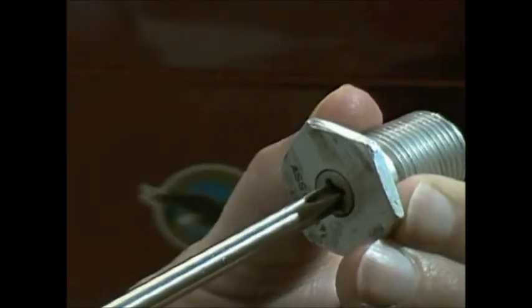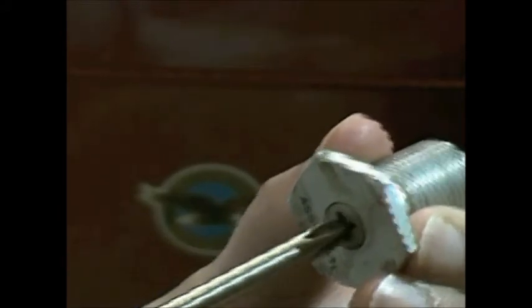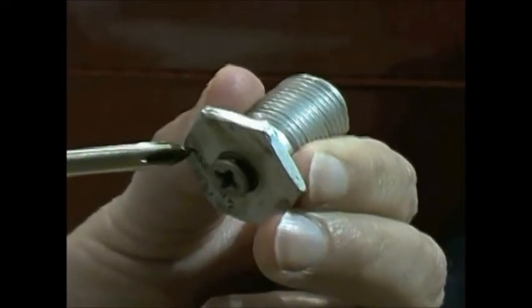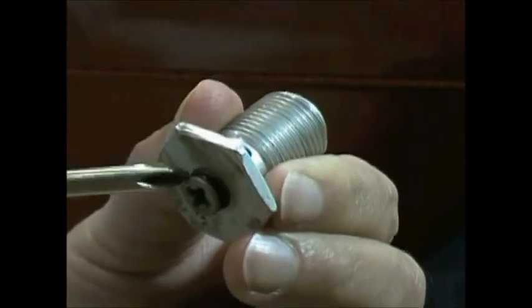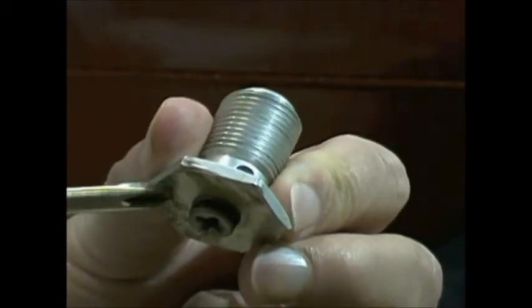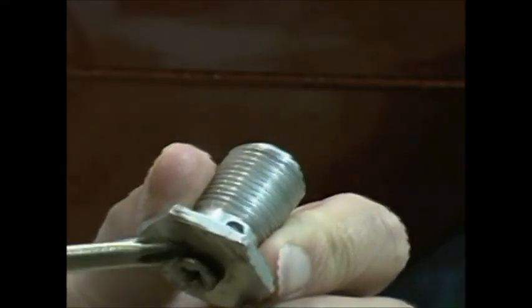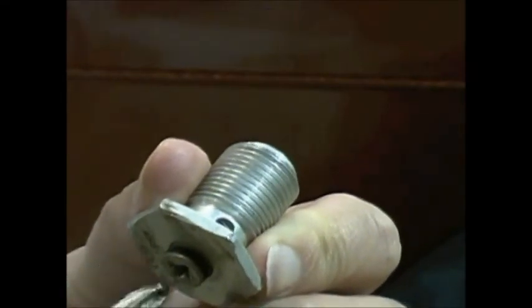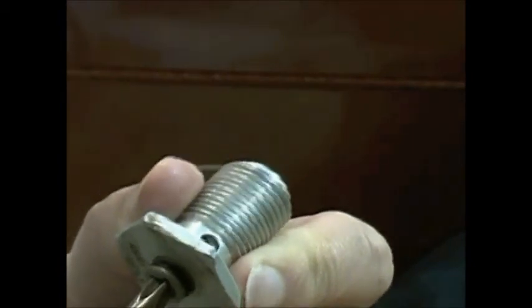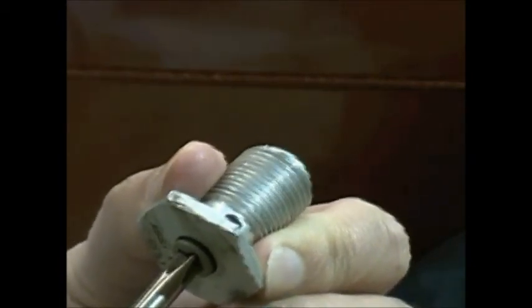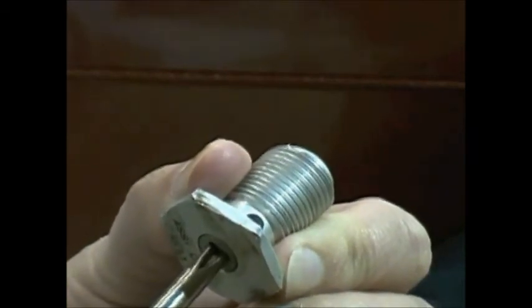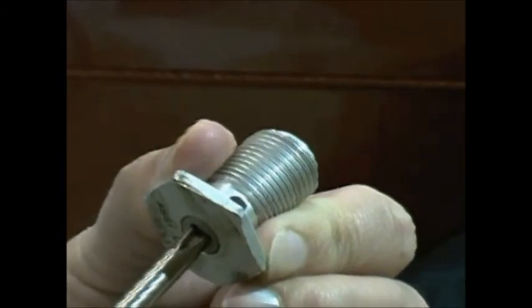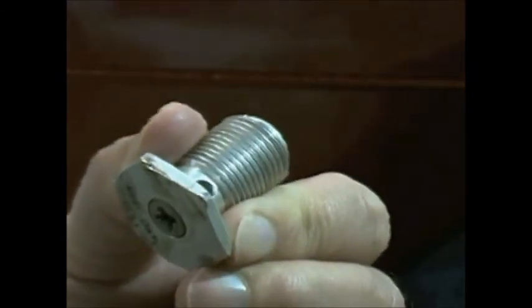to change the O-ring without defueling the tanks, you put your Phillips screwdriver in the slot and rotate a quarter of a turn clockwise. This will pop out your plunger with your O-ring exposed right there. And up inside the valve, there's another valve that closes when you pull this one out so that all the fuel doesn't come out. You carefully change it. Put a little bit of lube on it and carefully push in on it and rotate it counterclockwise a quarter turn to lock it back in place.